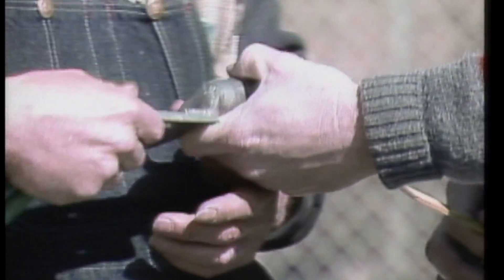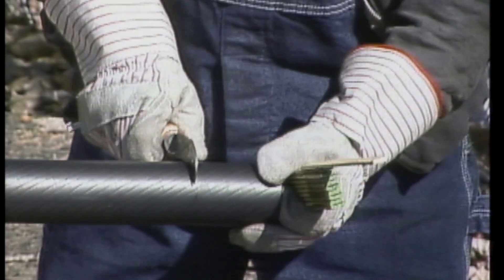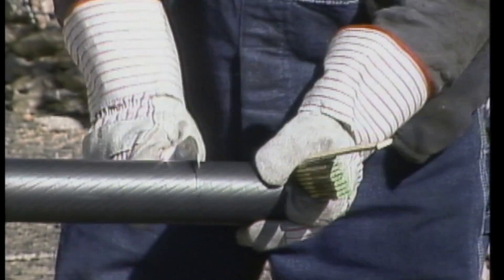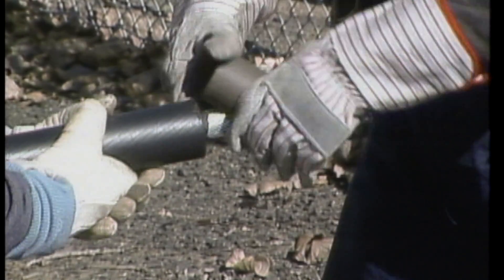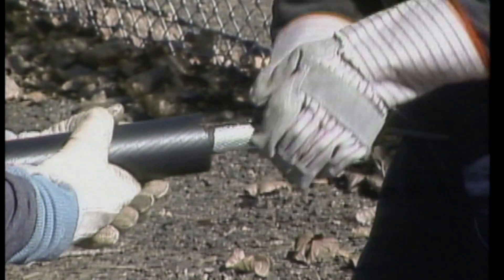They measure the inside of the lug, transfer the measurement to the end of the cable, and mark the cable. They cut the insulation and remove the insulation and the conductor stress control layer to expose the bare conductor.